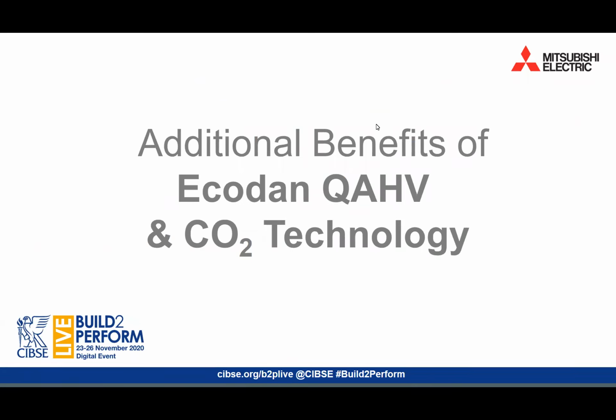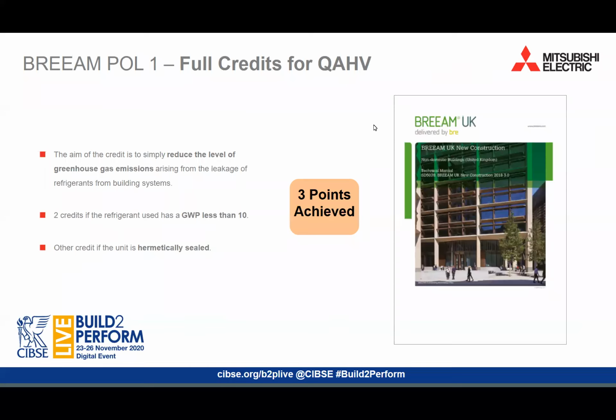So let's close now by looking at some of the additional benefits of QAHV and CO2 technology. Pol 1 is the BREEAM credit that deals with the impact of refrigerants. The aim of this credit is to reduce the level of greenhouse gas emissions arising from the leakage of refrigerants from building systems. There are 3 credits available, split into 2 assessment criteria. The first 2 credits can be allocated where the systems using refrigerants have direct life cycle CO2 equivalent emissions of less than 100 kilos per kilowatt cooling capacity, or if the refrigerant has a GWP less than 10. The other credit can be allocated if the unit is hermetically sealed or uses pump down. The QAHV is able to gain all 3 credits as it is hermetically sealed and uses a refrigerant with a GWP of only 1.